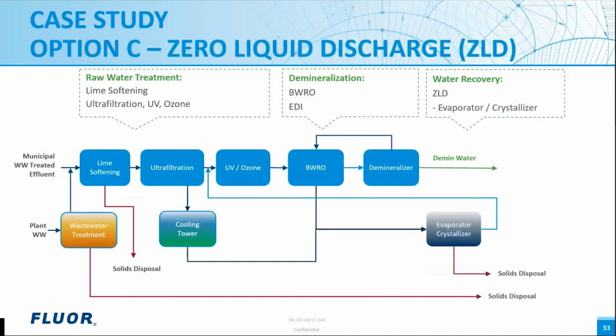Option C is the traditional zero liquid discharge to recover 100% of the liquid waste streams and has a solid stream that will be sent offsite for disposal. Technology considered for this ZLD system are evaporators and crystallizers. And option D is the same as option B, minimum liquid discharge. However, as mentioned, the difference is that it aims to recover 75% of the liquid waste streams from the plant and 25% shall be disposed to an off-site evaporation pond.